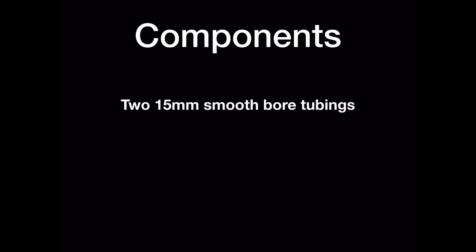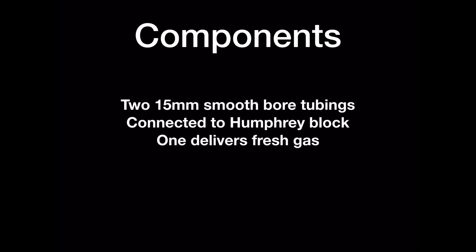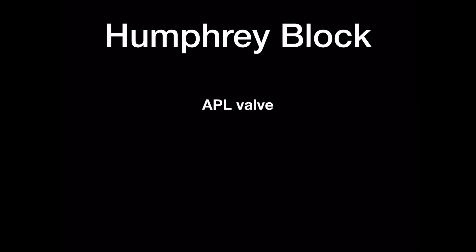Components. The Humphrey ADE system contains two lengths of 15mm smoothbore tubing connected proximally to the Humphrey block and distally via a Y connector to the patient. One length of the tubing delivers fresh gas flow whilst the other carries away exhaled gases.